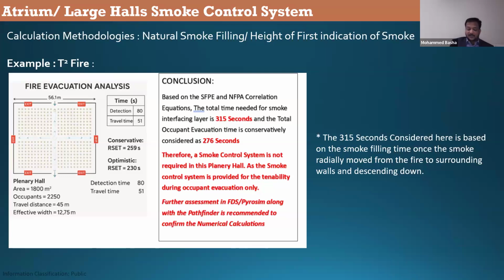If you look into our QCDD requirements or NFPA 92, the main purpose of providing smoke control is to have occupant evacuation tenability. If you achieve this, then why do you need to have a smoke control system? But the design of the system is so critical that you need to prove this via software. There are two software to be used here. One is Fire Dynamic Simulator, another one is called Pathfinder. Then it has to be submitted to the Civil Defense Authority having jurisdiction. They have to approve this. Then you can use this system.